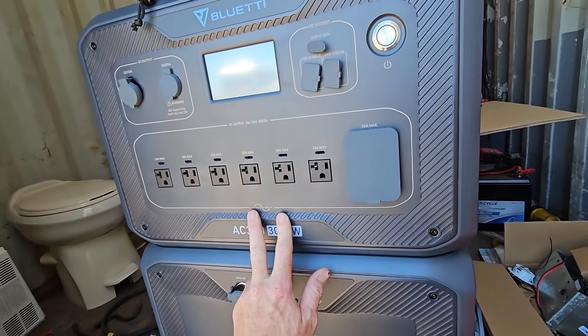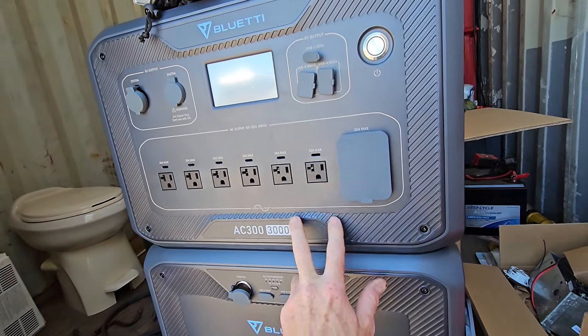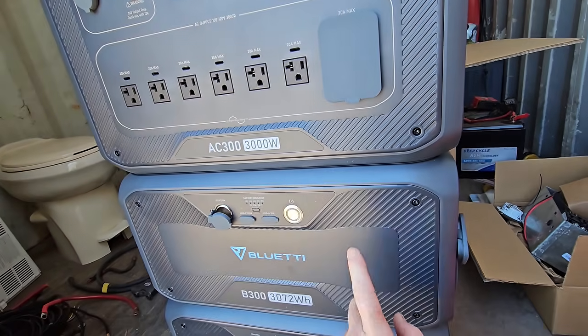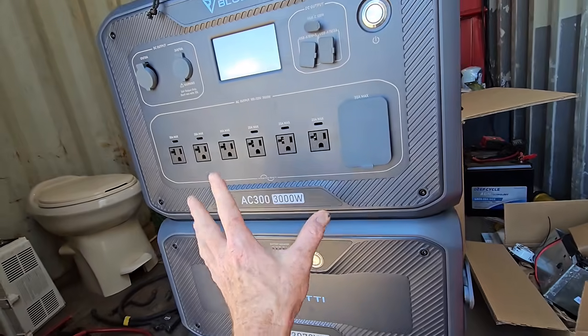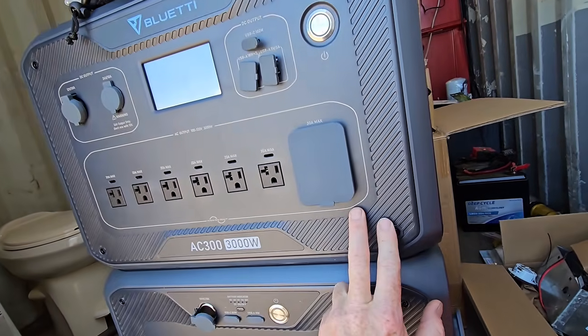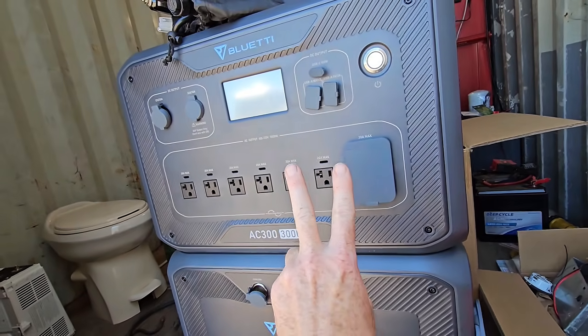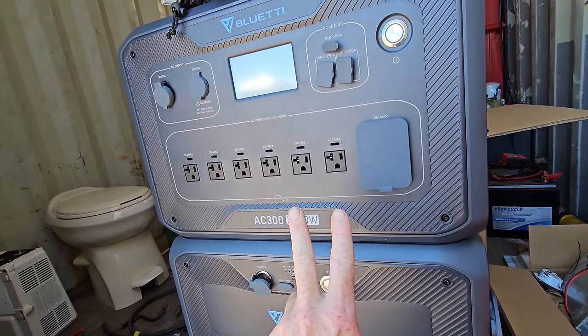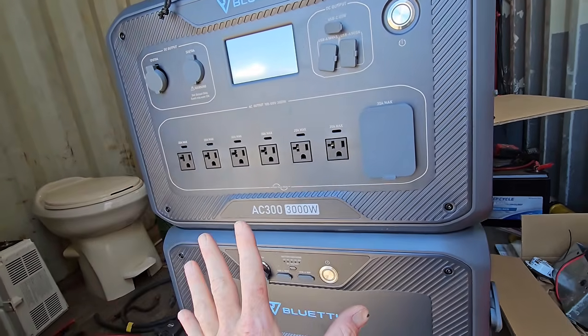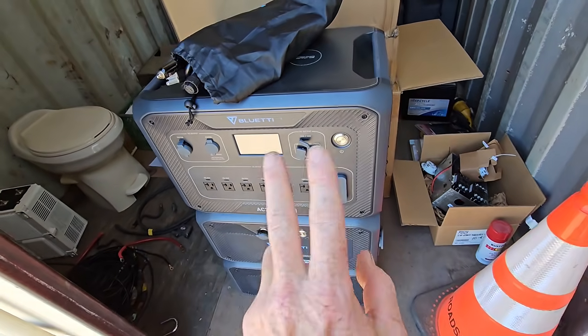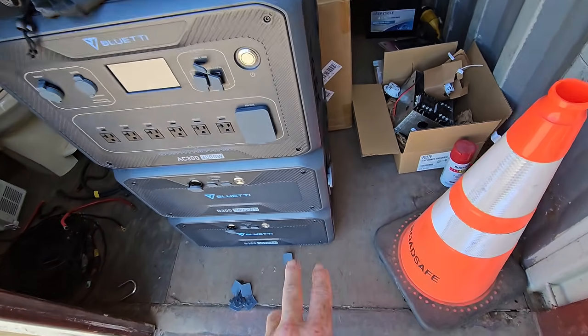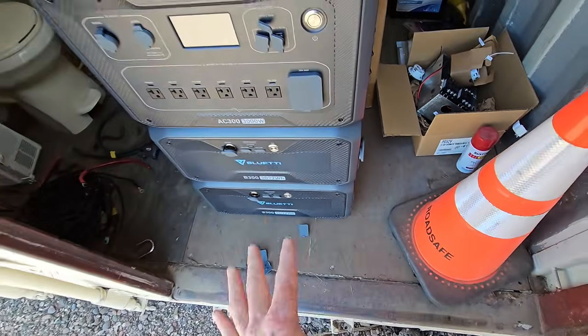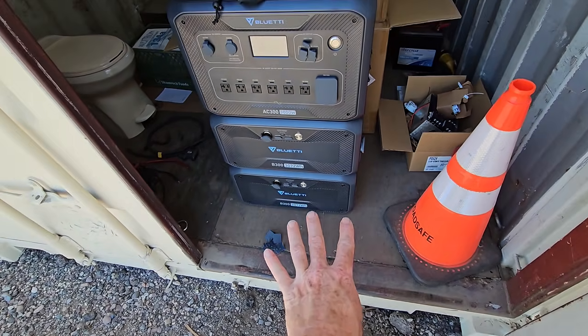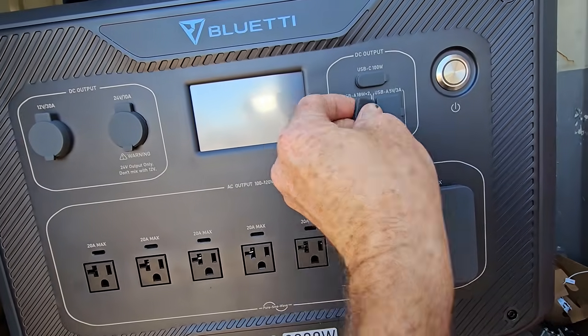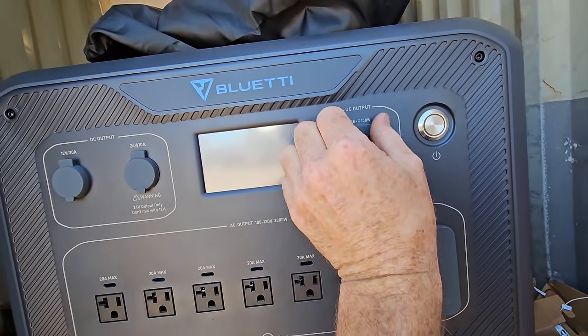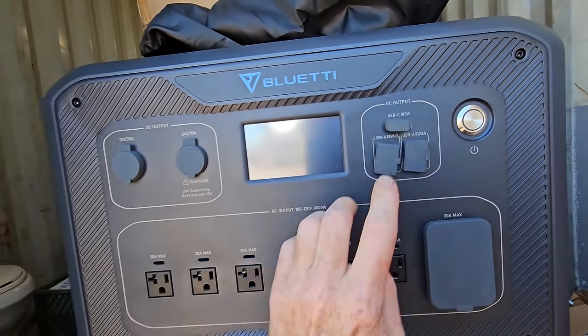The AC300 is not a standalone unit — it has no battery backup within it. You'll need at least one module for it to do anything useful, but it does have the inverter built in, with 2 MPPT charge controllers for a total of 2,400 watts of solar. You can charge the batteries below with it, and you can add up to a total of 4 batteries on this system. Otherwise you still have USB charging here and USB-C above.